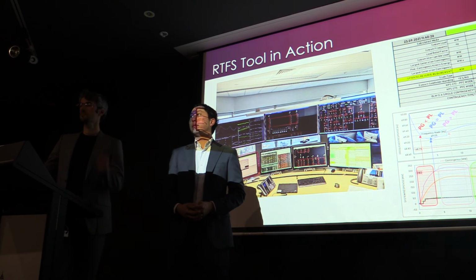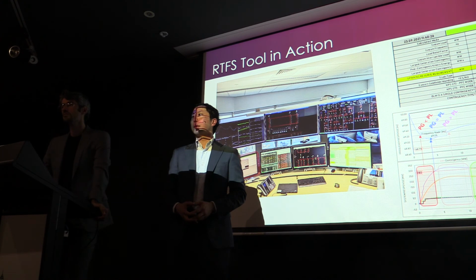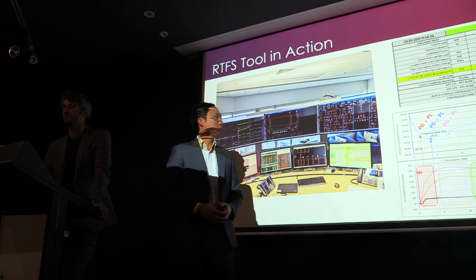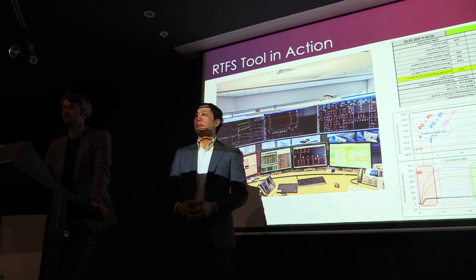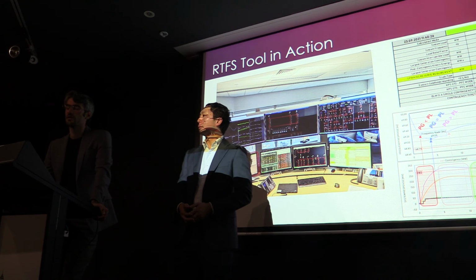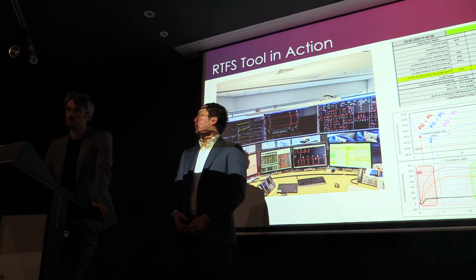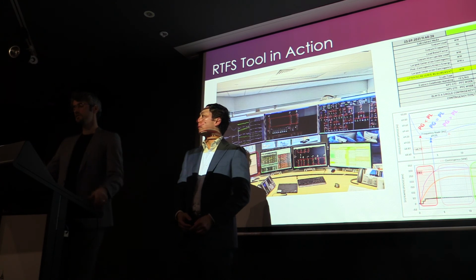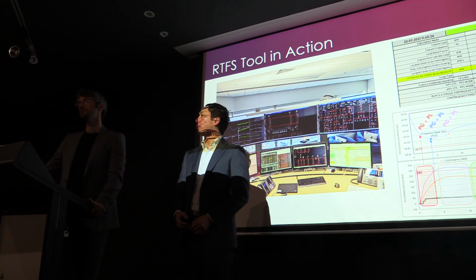And just in practice, if you've got, I don't know, 140 megawatts of spinning reserve, and it suddenly jumps for a reason, and it's saying, well, really you want 260 now. What's actually happening in real time at the moment? Like if it sits there saying your spinning reserve requirement is 260, and all we've got scheduled at the moment is 120, what are you actually doing about it in real time? It really depends which units are providing and how much inertia we've got. So you might have, for example, two units in min-gen, so they can provide full headroom.